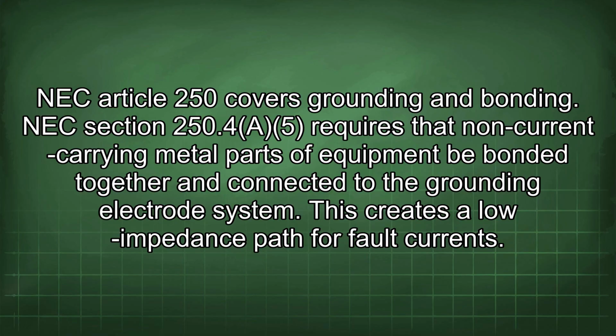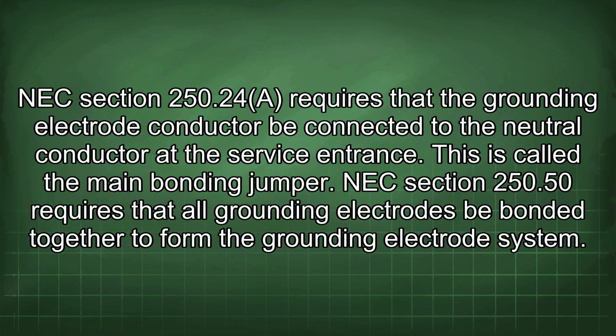This creates a low impedance path for fault currents. NEC section 250.24 requires that the grounding electrode conductor be connected to the neutral conductor at the service entrance. This is called the main bonding jumper.